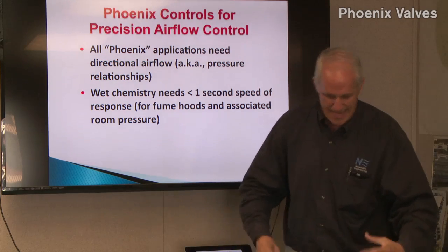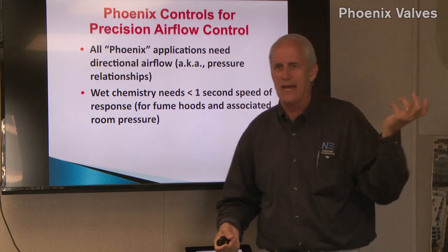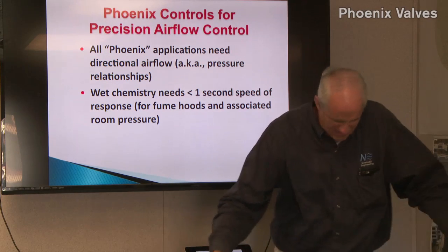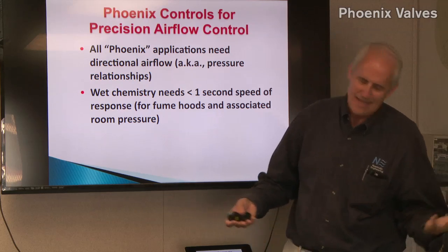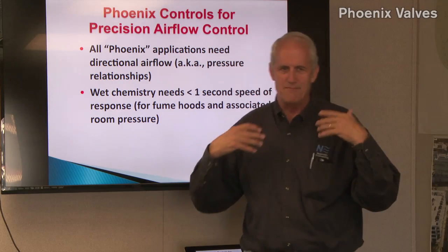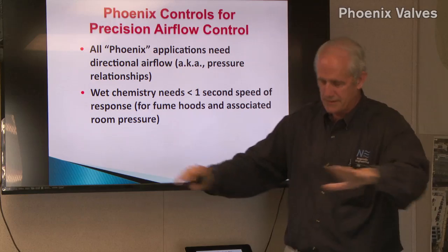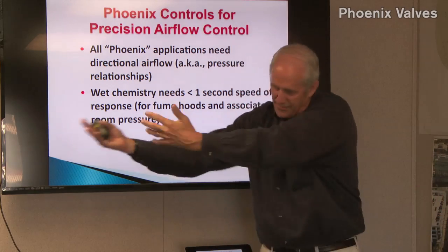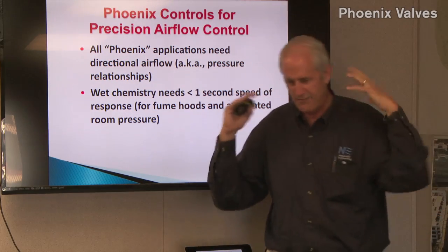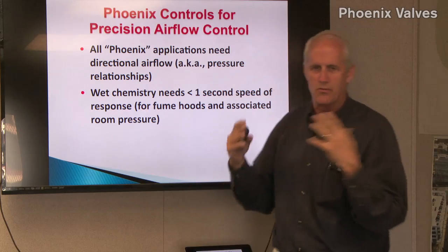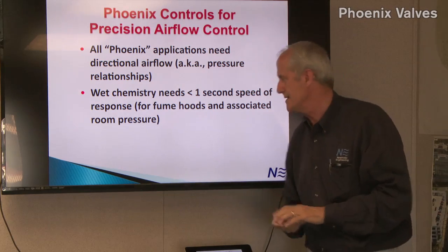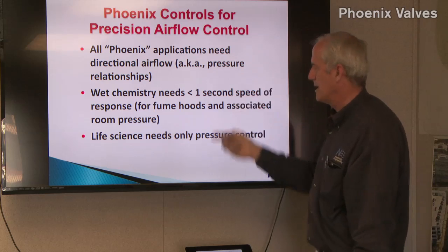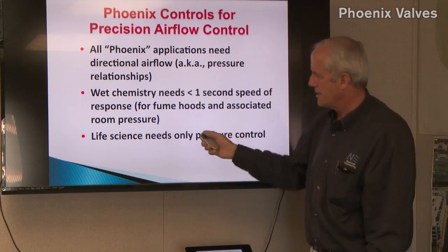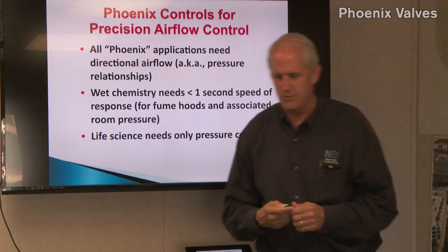If you've got these animals, which these transgenic mice could be worth $100,000 each, so you've got all these little critters in these little boxes, you better not muck up. So we keep the positive room positive if they're immune compromised, so we don't bring anything bad through the doorway. If they do have some sort of outbreak, we can pull the room negative so that you maintain the space pressure in that case. Wet chem we don't have here. Really what we're talking about is pressurization control in the room.